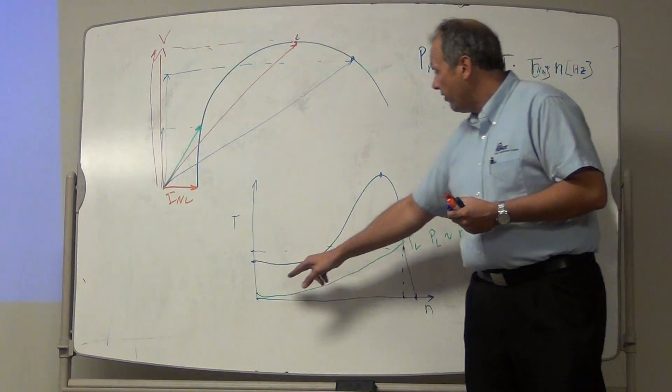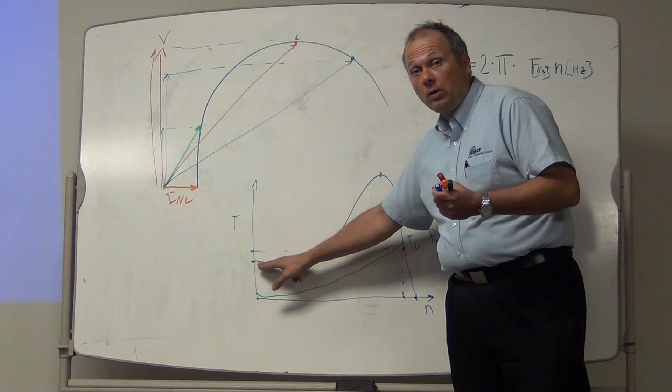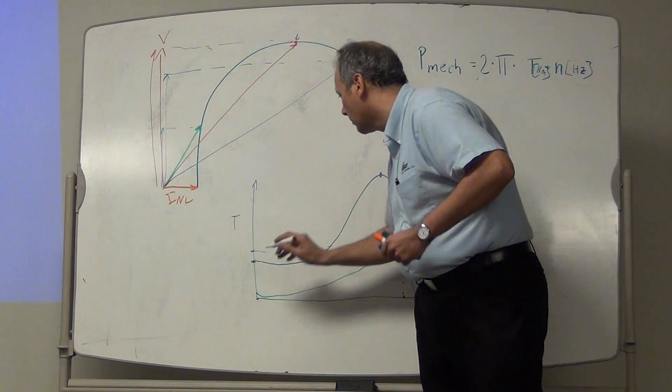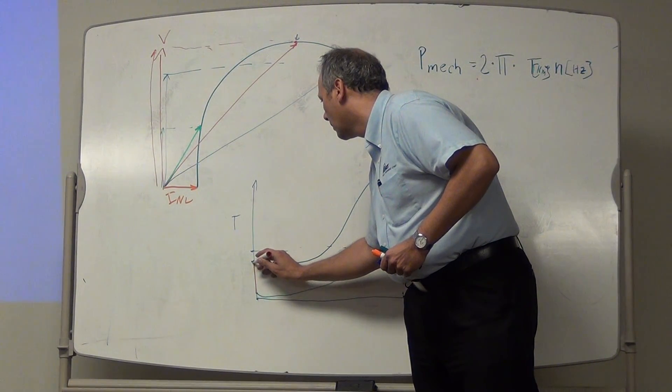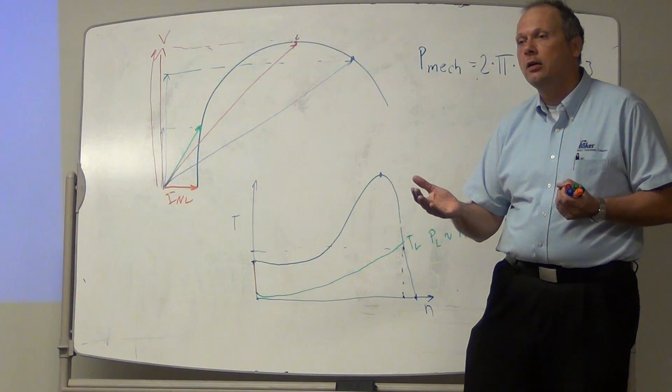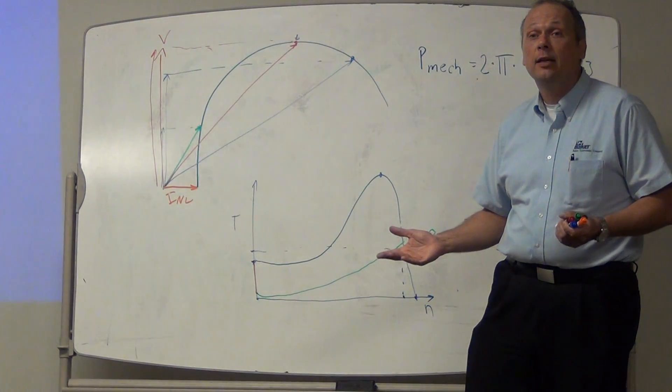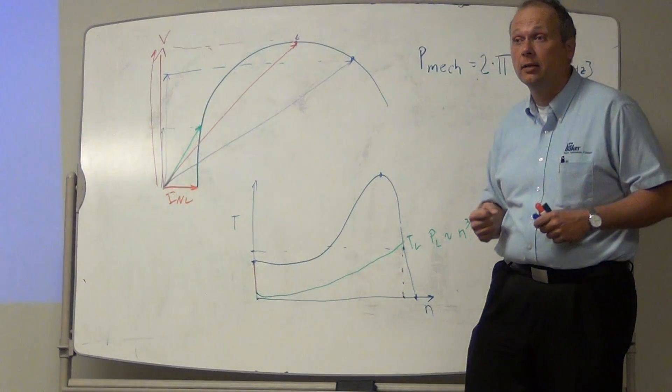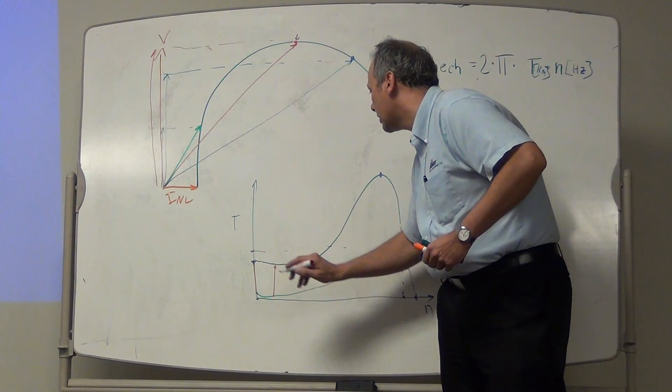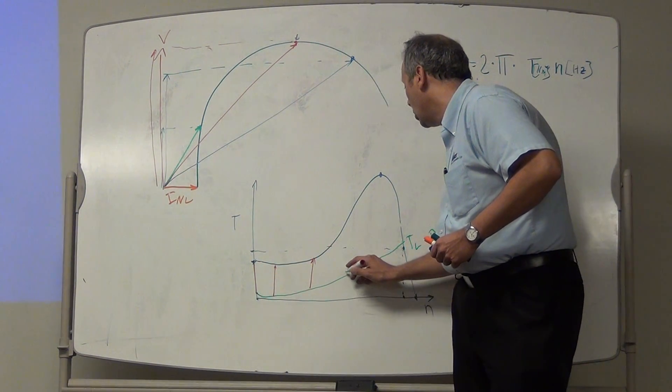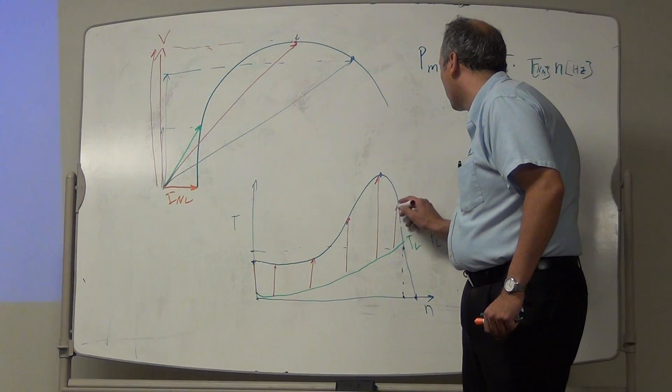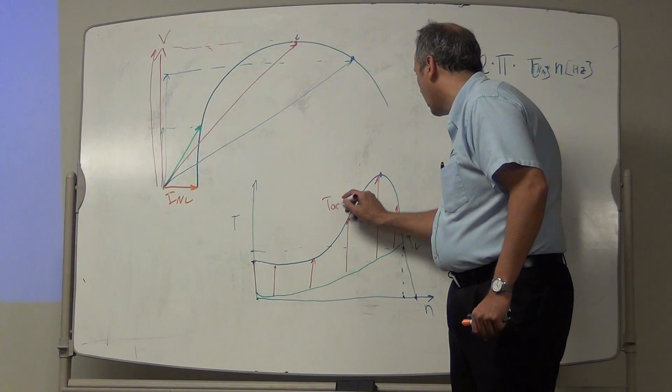Well, if I have more torque available by the motor than the amount of torque that the load demands, I have this delta right here. As long as the motor pushes harder than the load is requesting, only one thing can happen, and that is that the load starts accelerating. So as long as I have a positive distance between my green and my blue lines, I have an acceleration torque, T acceleration.